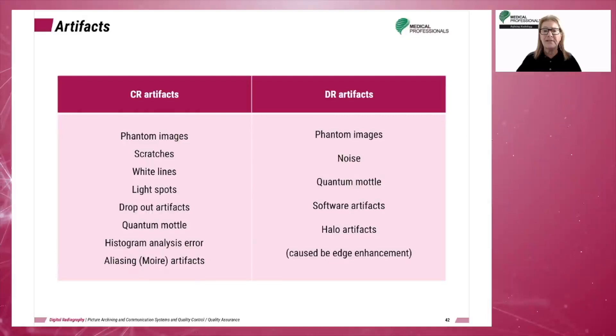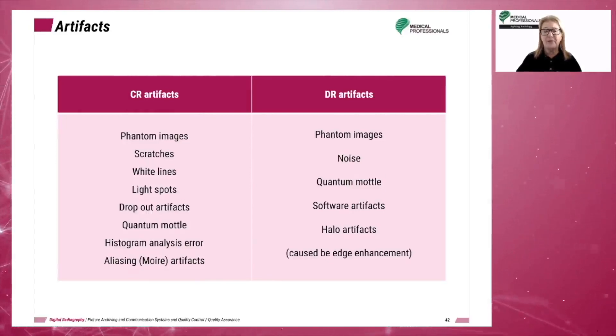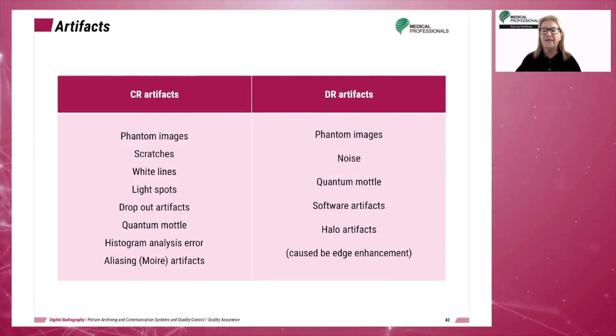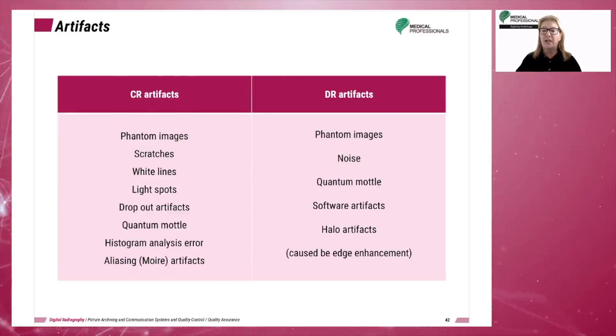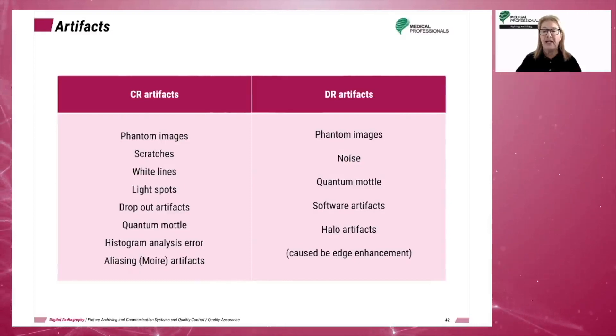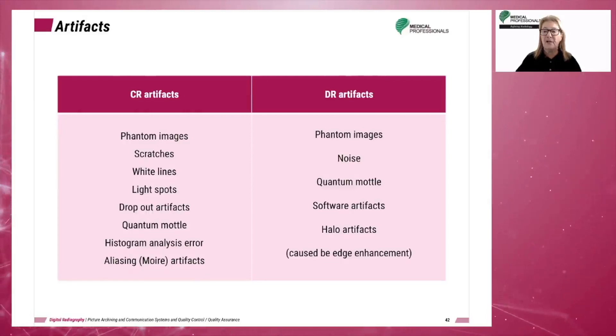Artifacts occur in both CR and DR imaging systems. The most common source of CR artifacts is the imaging plate, while artifacts appearing on most or all images are typically the result of problems with the plate reader. DR system artifacts may be caused by electronic faults in the detector elements, or DELs, and by software problems. Electronic artifacts randomly occur on DR images for a variety of reasons, including bucky motor interference, x-ray tube rotor initiation, extraneous radio frequency signals, and other electronic interferences.